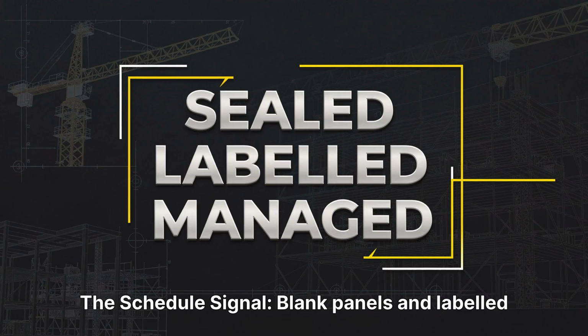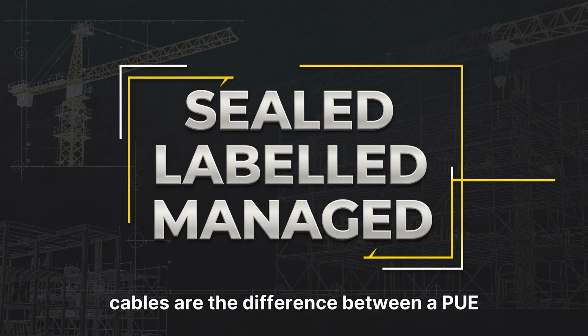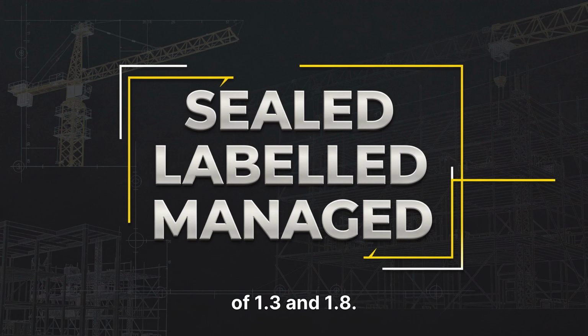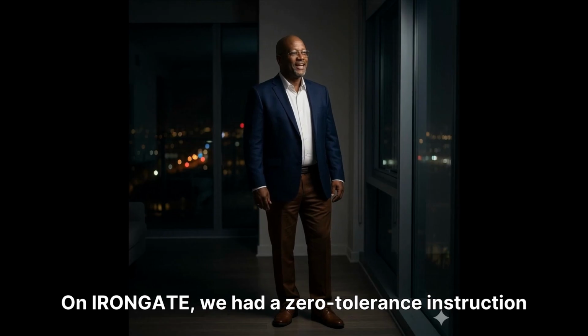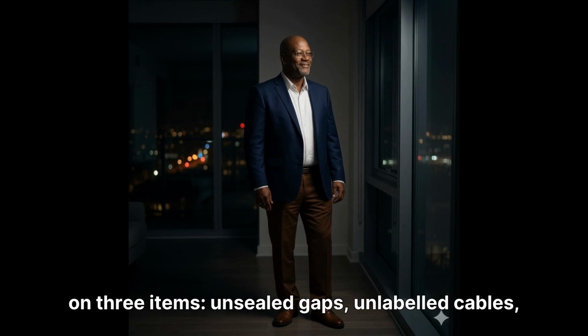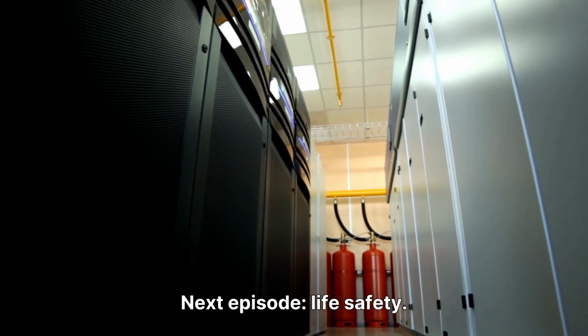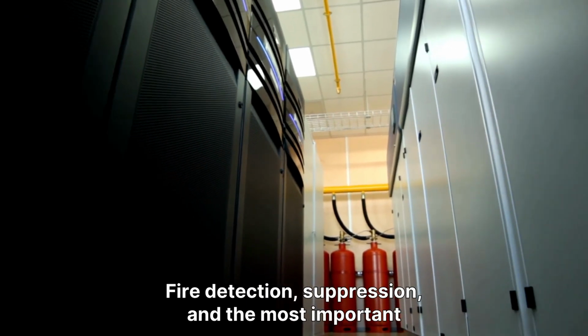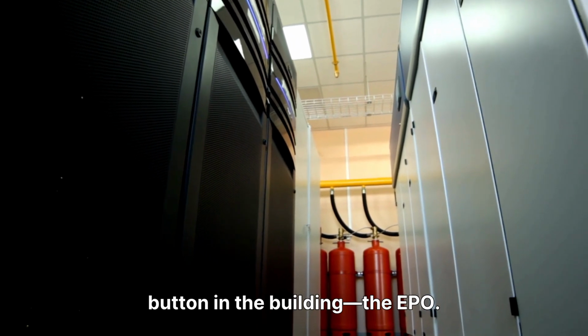The schedule signal. Blank panels and labeled cables are the difference between a PUE of 1.3 and 1.8. On IRONGATE, we had a zero tolerance instruction on 3 items: unsealed gaps, unlabeled cables, and missing panels. These were tracked on a daily defect log with same-day resolution required. No exceptions were made. Next episode, life safety, fire detection, suppression, and the most important button in the building, the EPO.